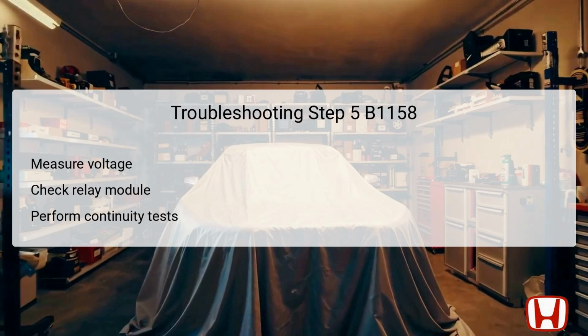If battery voltage is present at these terminals, this indicates that power is reaching the relay control module, guiding you to further diagnostic measures. If voltage is absent, it points towards an issue in the power supply circuit, which necessitates closer examination. This step is critical, as it determines whether the problem lies with the power supply or within the module itself.